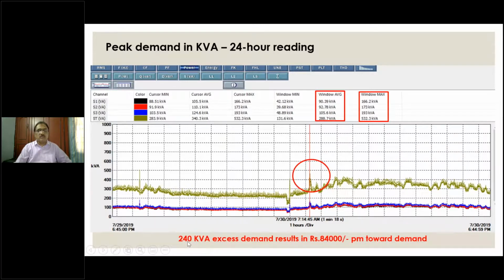That means 240 kVA in excess, and that is about 84,000 rupees per month. So 240 kVA, the difference between the two, and it is showing 84,000 rupees as money available if they discipline the starting of equipments, reducing the incidence of peaking of kVA. For example, here at 1445, maybe the AC air conditioning chiller must have been started, and that is the reason why a peak has been registered in the kVA.